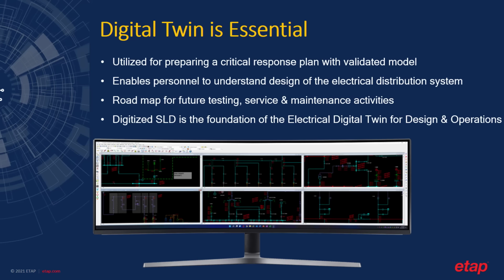Creating a one-line diagram is the first step in preparing a critical response plan, enabling electrical personnel to fully understand the layout and design of the facility's electrical distribution system.